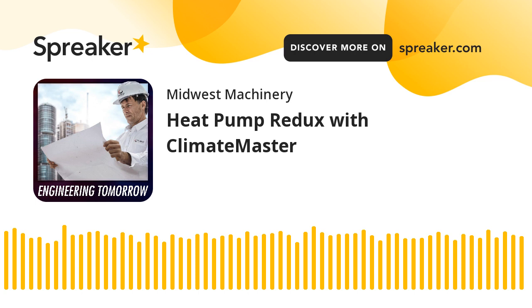So we have to have a cooling source or some type of heat rejector. The heat rejector is used to maintain the system water temps below 90 degrees. So we have the boiler, that's helping us maintain above 60, and then the heat rejector is helping us maintain it below 90. A typical heat rejector for a closed loop system is a cooling tower. Now, the goal is the system.